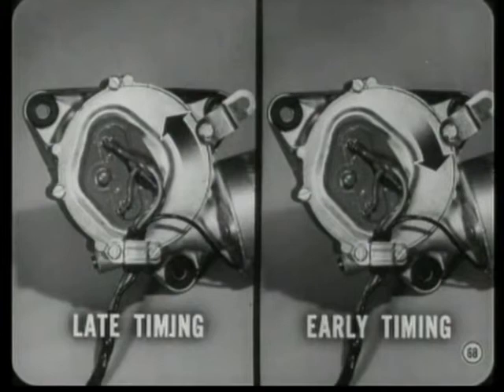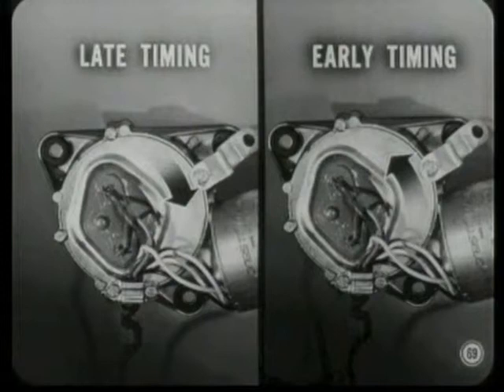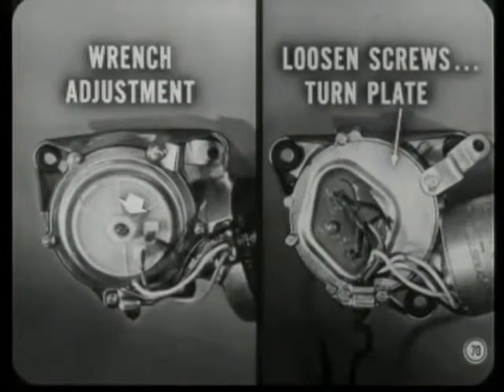To adjust the park timing on either single-speed motor, loosen the 5 retaining screws on the gearbox and turn the metal cover plate. Turn the plate to the left if timing is late, or to the right if timing is early. On variable speed motors, the adjustments are made in the opposite directions. We have 2 different suppliers of these variable speed motors, Bob. There's a little difference in the adjusting procedure. One motor has a nylon plate with a hex in the middle to take a wrench. On the other, you loosen the 5 screws and turn the metal cover plate.